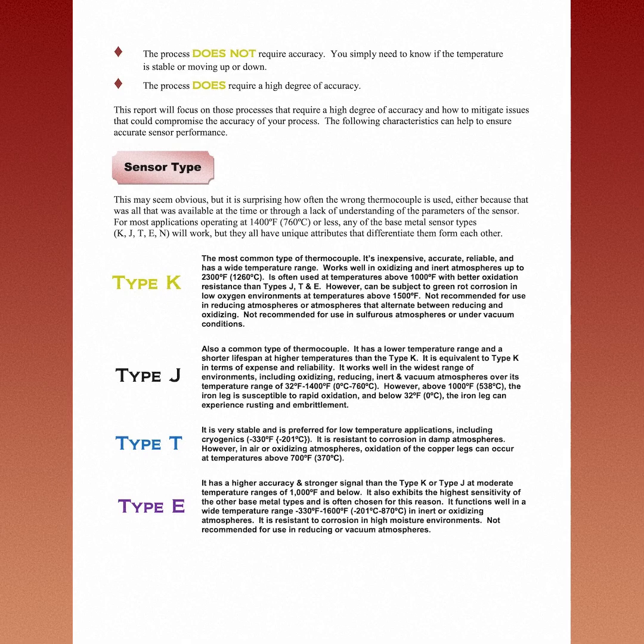Sensor type. This may seem obvious, but it is surprising how often the wrong thermocouple is used, either because that was all that was available at the time or through a lack of understanding of the parameters of the sensor. For most applications operating at 1400 degrees Fahrenheit or 760 degrees Celsius or less, any of the base metal sensor types, K, J, T, E, and N, will work, but they all have unique attributes that differentiate them from each other. Type K, the most common type of thermocouple.